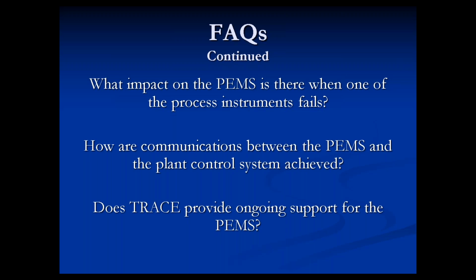Well, if one of the Tier 1 components fails, our PEMS software automatically flags that and elevates one of the parameters from Tier 2 into Tier 1. And we make use of that. Once that primary instrument is repaired, it goes back into being one of the Tier 1 parameters used. So there are inherent levels of security that the PEMS deploys, where in a CEMS, if an analyzer fails, you're out of luck. With the PEMS, we've got multiple layers of security, so the PEMS still operates well in the event of process instrument failure.